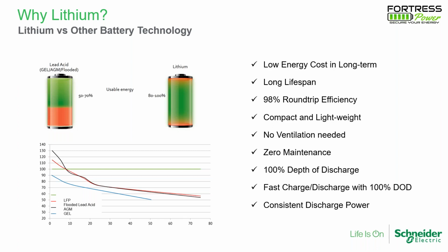And it also supports a fast charge and discharge function too. During the discharge cycles, most of the time on lead acid you lose power a little bit, and then at the end of the discharge curve you see the power drop quite a bit because the voltage drops. In the lithium battery, particularly lithium phosphate, our curve is super flat. So if it is 5 kW, you will get 5 kW from beginning to the end, a consistent power output to the system.